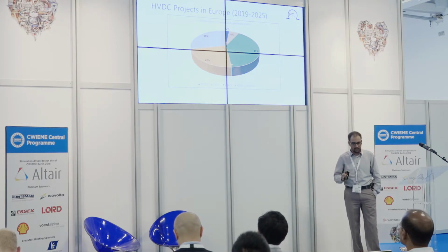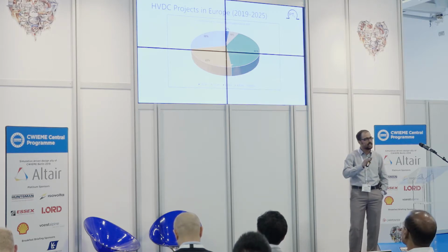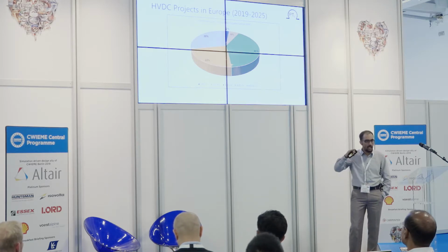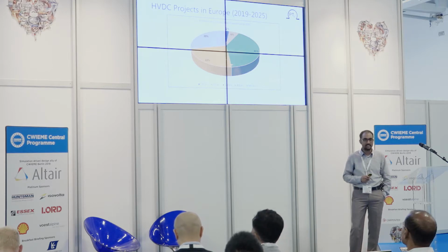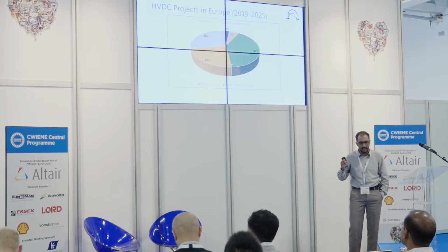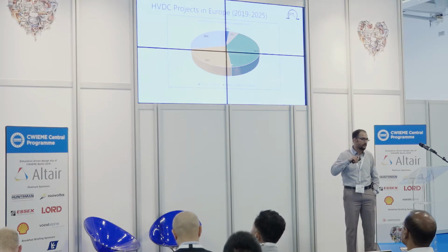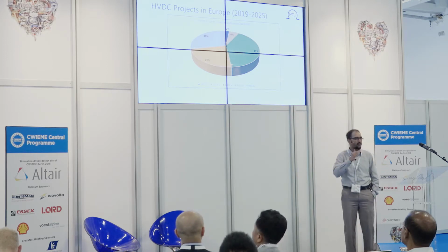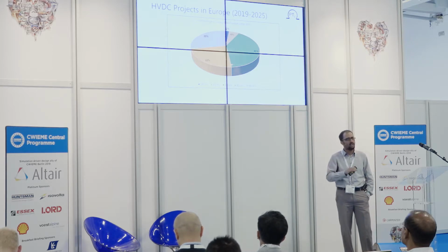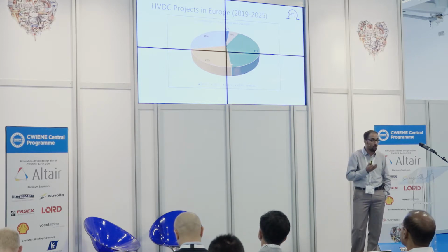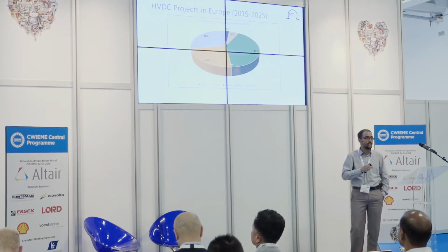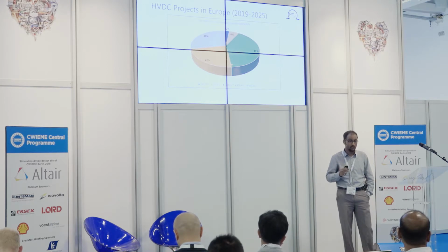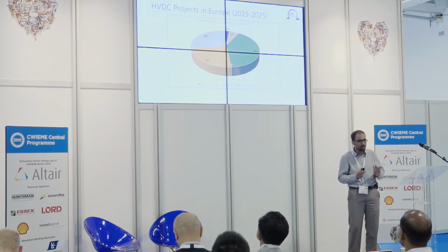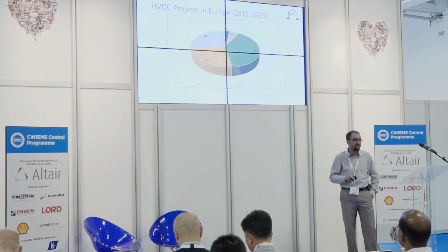The voltage categories we see are mainly between 200 and 500 kV, still the medium range, because in HVDC the highest voltage achieved is 1100 kV, and utilities and system operators are planning to go even higher. That's happening in countries like China and India, where the main reason for these projects is to transfer power from generation centers to load centers over extremely long distances, more than 2,000 kilometers. That requires higher voltage, and the older thyristor-based technology is the only one good enough to withstand those voltages. However, the newer, more flexible technology is preferred by utilities because it really reduces the overall footprint of the station, though it can only withstand these lower voltage ranges.